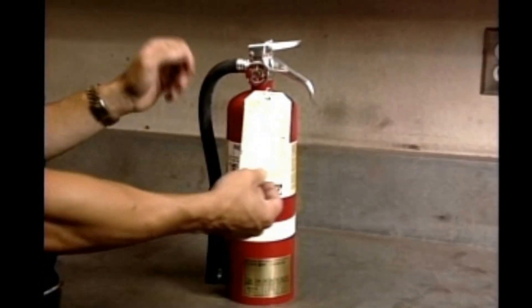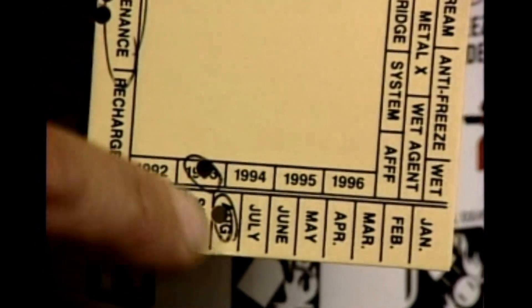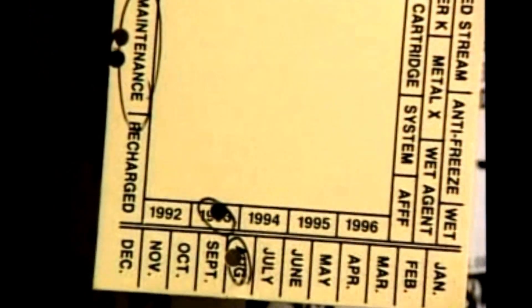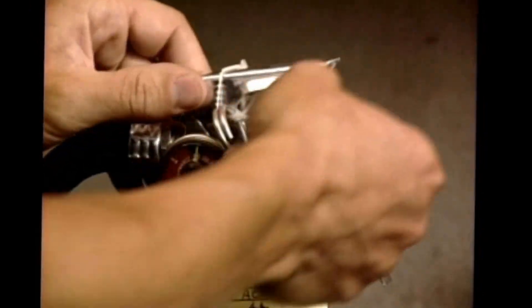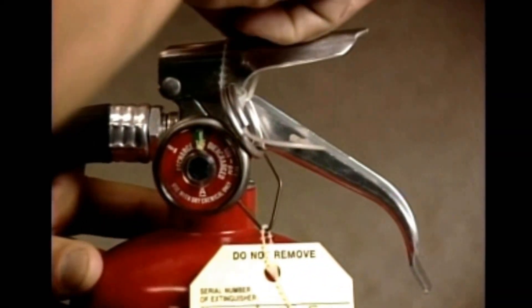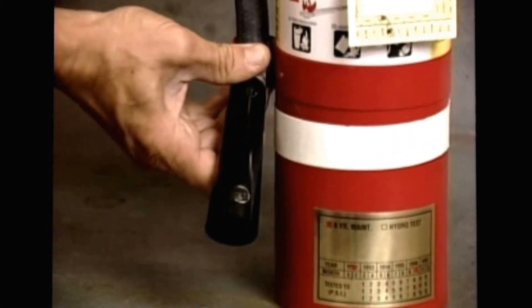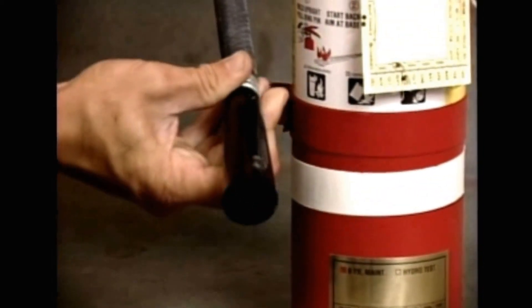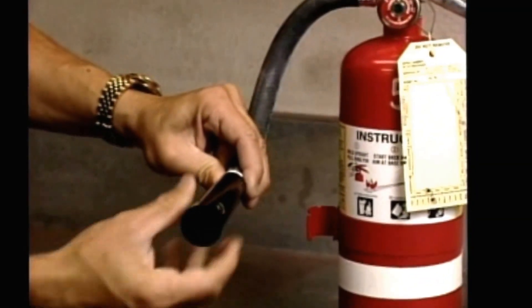Inspect serviceability by first checking the inspection tag and noting the date of the last inspection, maintenance, or recharging. Examine the lock pins and tamper seals to see if it has been actuated or tampered with. Look for any physical damage that might impair its operation. Check the discharge nozzle or horn for obstructions, cracks, or dirt accumulation.